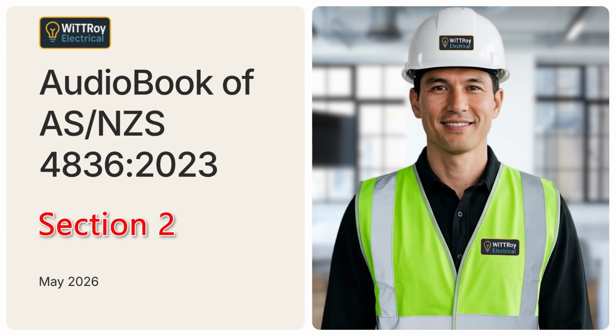Clause 2.3.4 Arc blast and flash injuries. Clause 2.3.4 explains arc blast and arc flash risks. Arc blast and arc flash must be considered in the design, operation, and maintenance of electrical installations. A person working on or near energized conductors or electrical equipment can be seriously injured or killed by arcing faults. Arc flash can produce extreme heat, bright light, pressure, molten metal, flying debris, and a plasma fireball. The heat energy that reaches the worker is called incident energy. Incident energy can cause serious burns. It can also ignite clothing or PPE if the clothing is not suitable for the hazard.